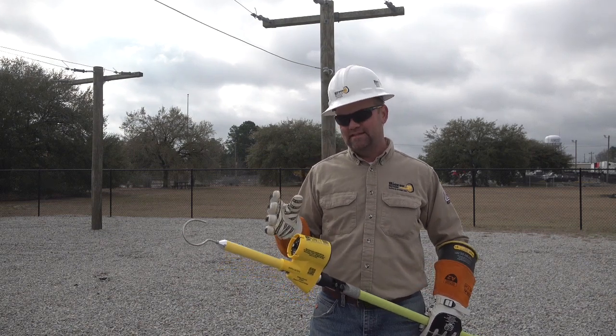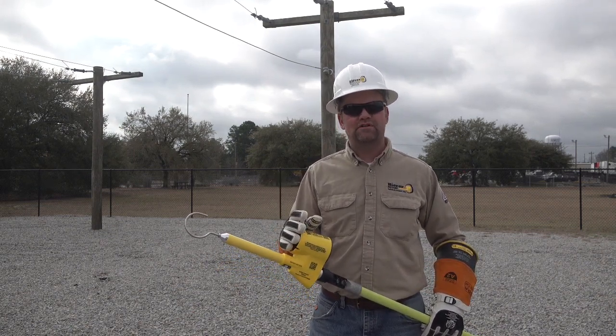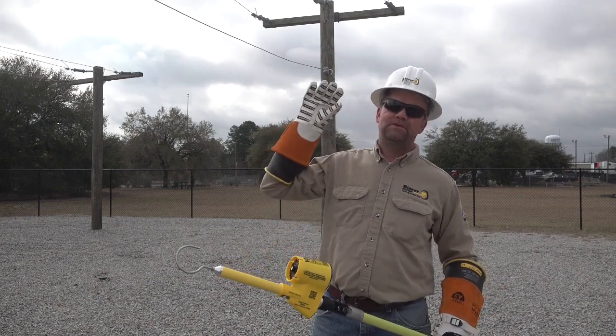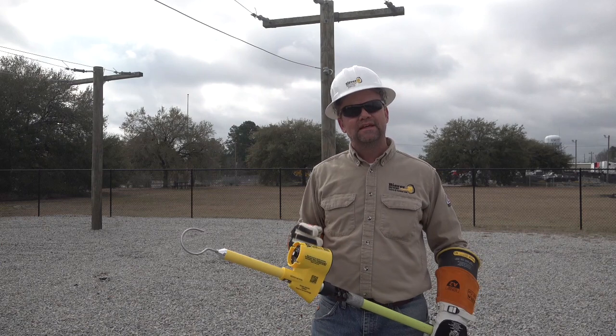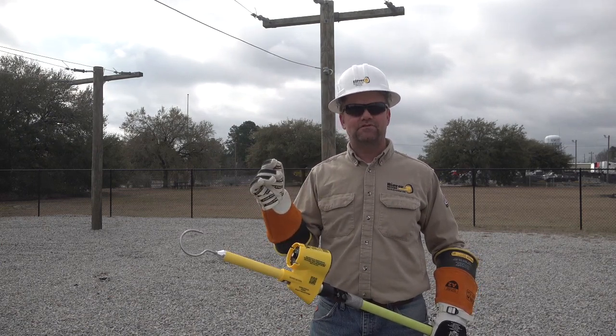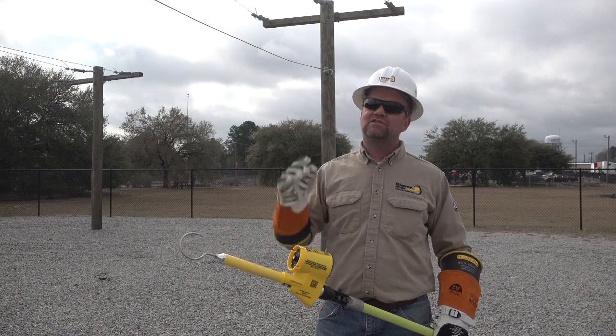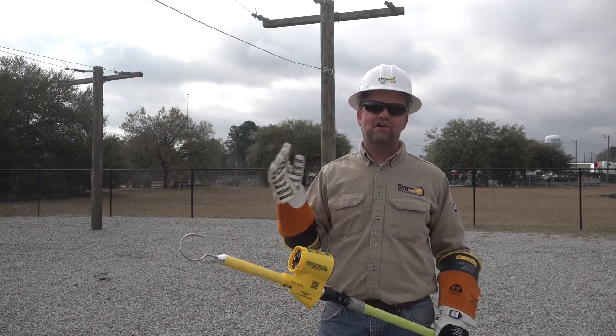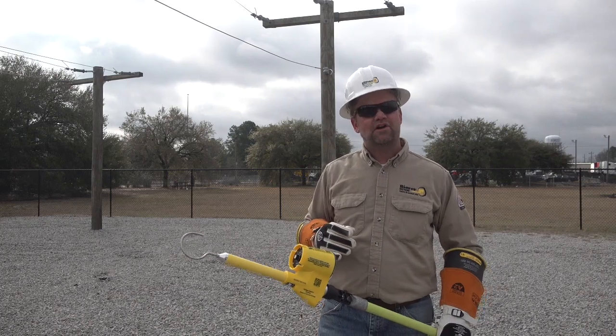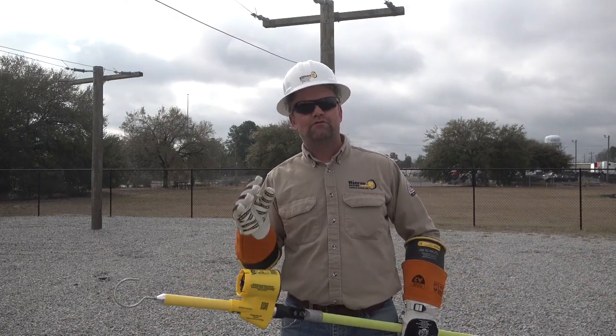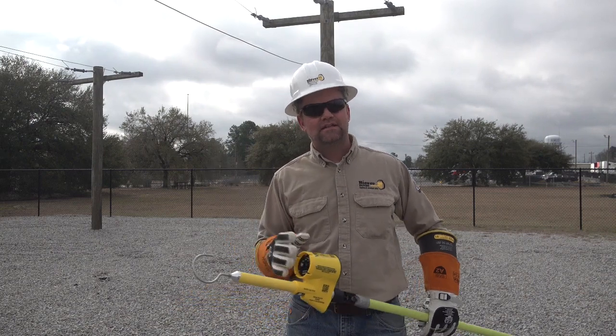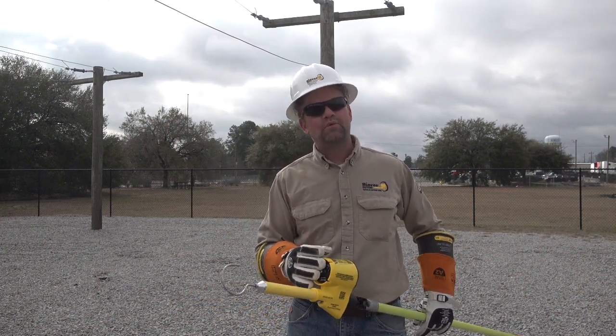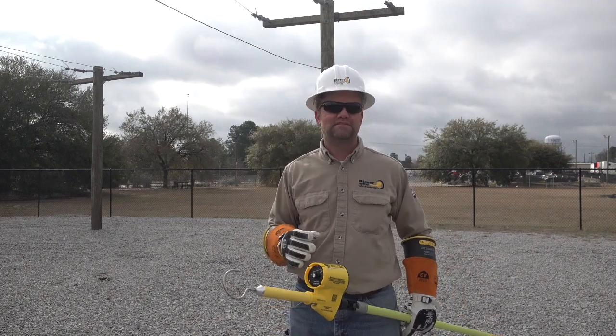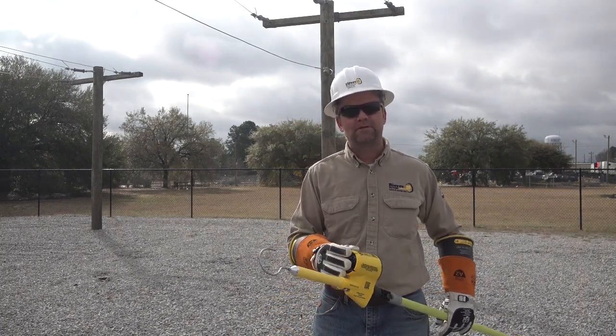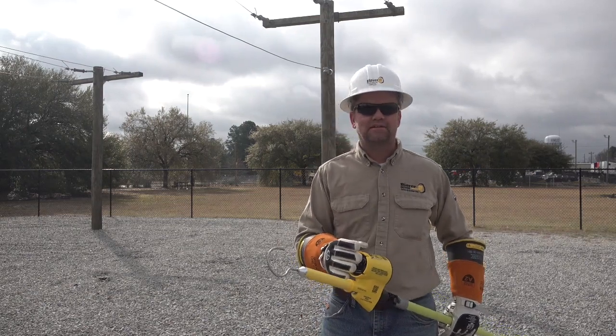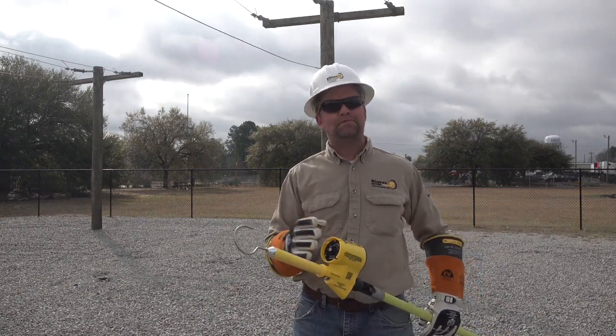The reason being is that it's a capacitive charged hold feature. So in other words, if I put it on a low potential like this 13.8 phase to ground, it's going to take a long period of time for that capacitor to charge. So the user may think there's no potential on the line because of that long delay. So again, we highly encourage the device to only be used on 40 kV and higher in the hold switch position. So we will not utilize that switch position here today because again, it will take a long time for the device to charge up, and I can't really demonstrate the light, the second on switch position, simply because we're in daytime.